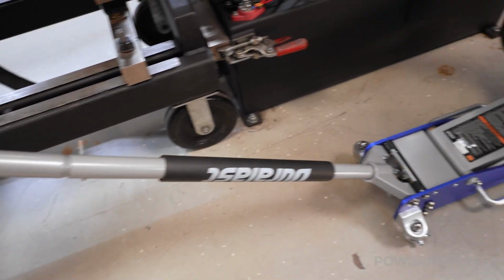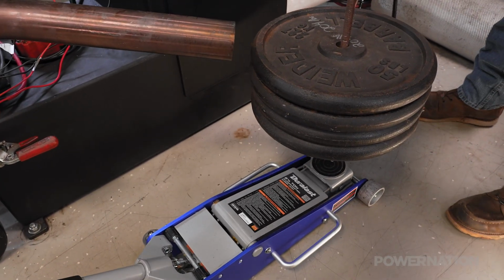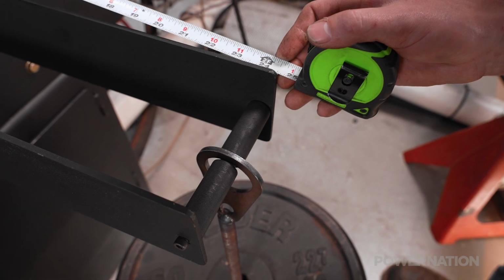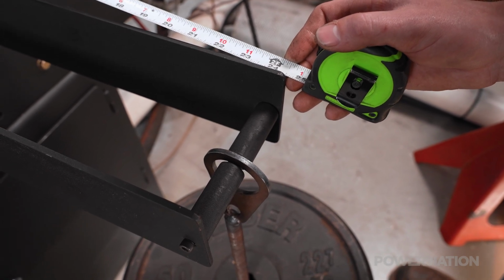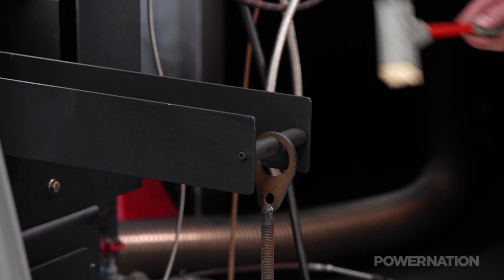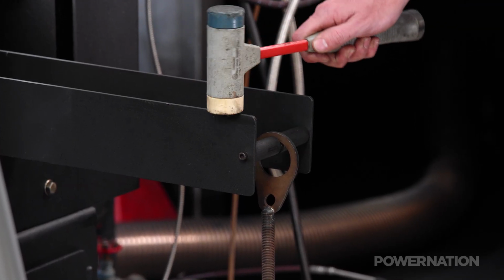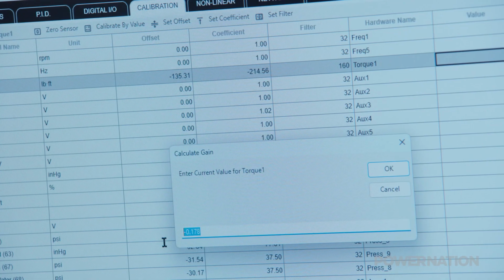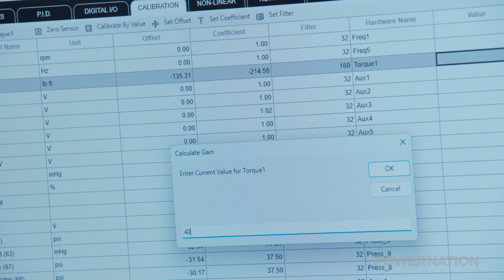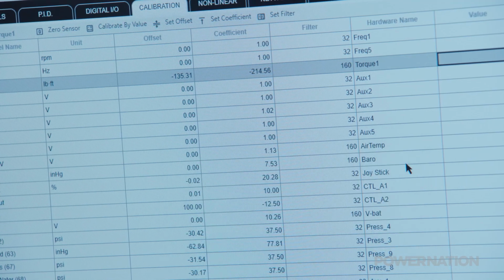Our weight is 204 pounds total, and since it hangs 24 inches from the center of the brake, we know it is applying 408 pound-feet to the absorber. After gently tapping the hanger to prevent any hysteresis or binding from affecting the reading, we can enter that value to calibrate the sensor in the software.